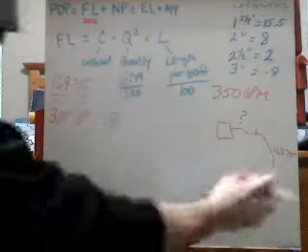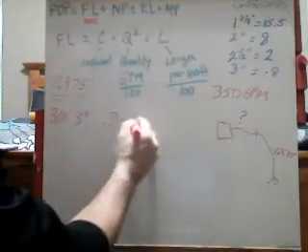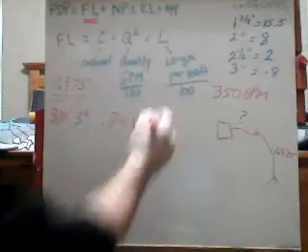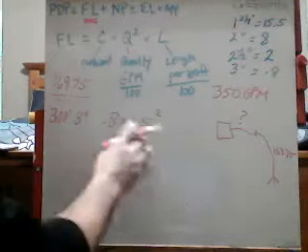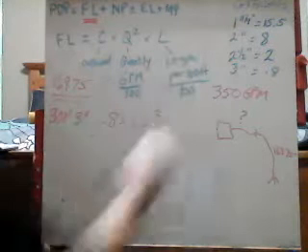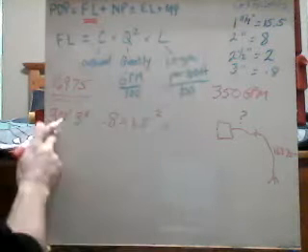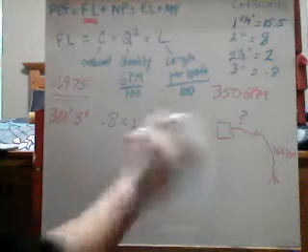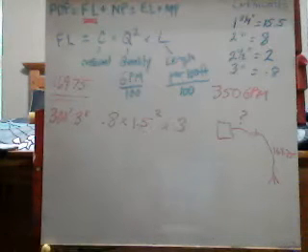Our quantity is still the same. We're still flowing only 150 GPM. So we do 1.5, because remember, it's really 150, and then we move the decimal point over, or divide it by 100. This time we're doing 300 feet, so it's 300, move the decimal over twice, or divide it by 100.